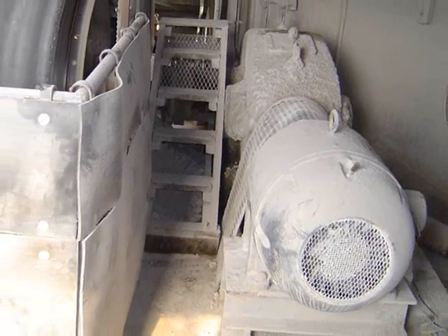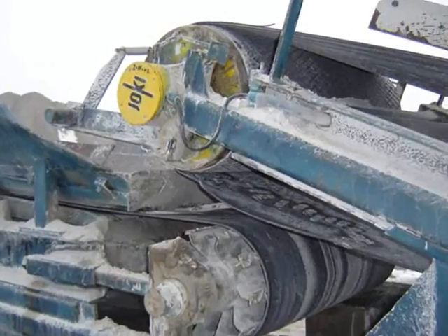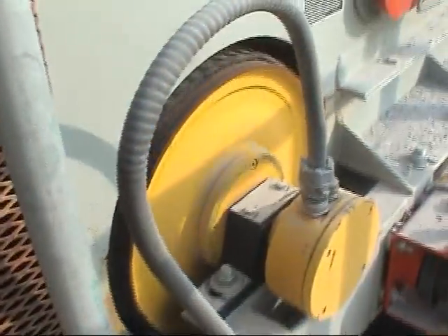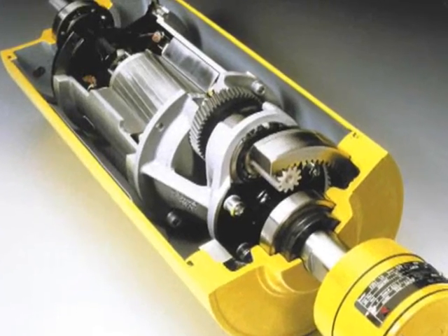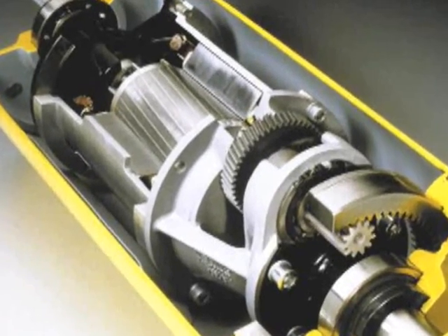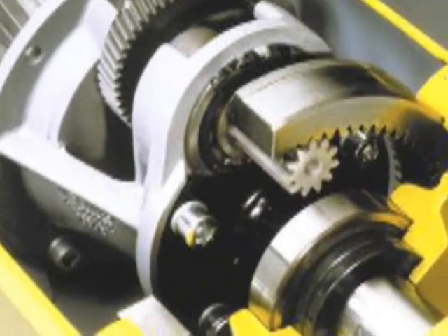Plant designers and operators have a solution: the Rulmeca Motorized Pulley. Continuously improving a concept developed in the 1950s, Rulmeca's motorized pulley solves conveyor drive problems impossible to address with the old-fashioned exposed drive concept. It consists of an AC squirrel cage induction motor coupled to a strong and efficient gearbox, hermetically sealed within an oil-filled pulley shell.